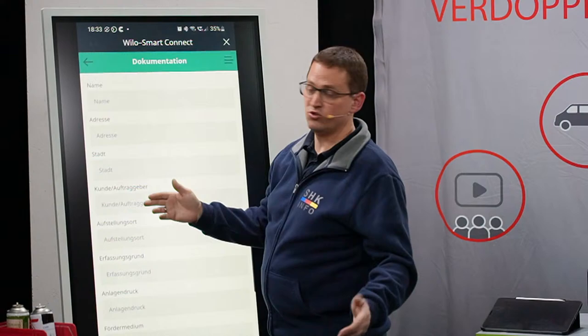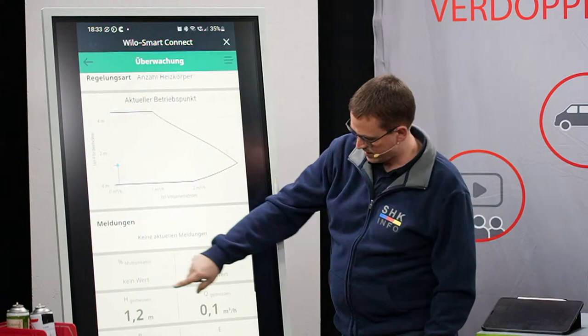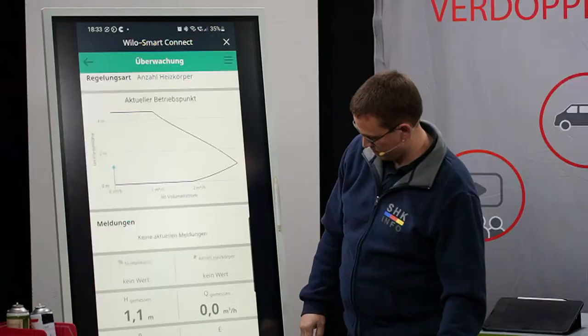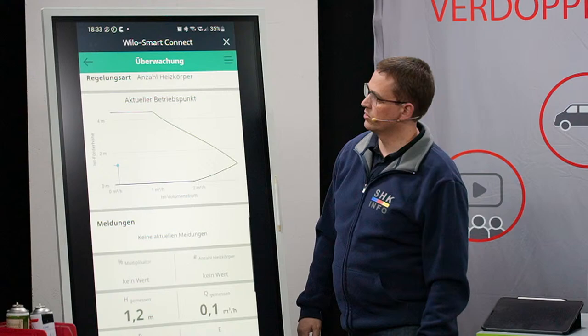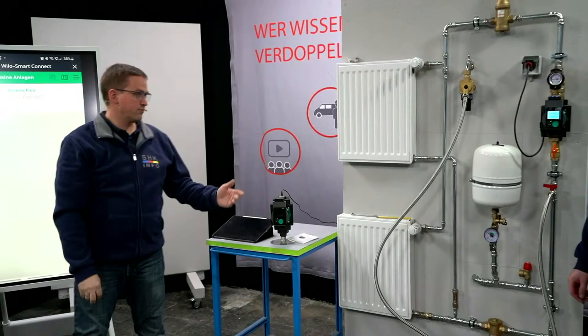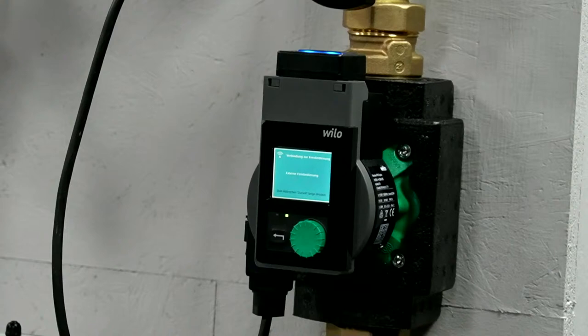Überwachung haben wir noch – da können wir den Betriebszustand beobachten. Man kann hier genau sehen, welche Werte die Pumpe aktuell liefert. Hier vorne kann man sehen, welche Kurve da arbeitet. Wir spielen jetzt nur am Thermostatventil – echt eine super Sache, und das alles in Echtzeit. Hier sieht man die aktuelle Leistung, den Energieverbrauch, den Volumenstrom. Das ist schon echt eine tolle Sache. Großes Display haben wir. Das Vollgrafik-Display ist natürlich echt wichtig – man kennt es von Pumpen, dass man einen Fehlercode angezeigt bekommt und dann recherchieren muss. So haben wir einfach die Möglichkeit, direkt an der Pumpe zu erfahren, was Phase ist, wo wir nachhaken müssen.